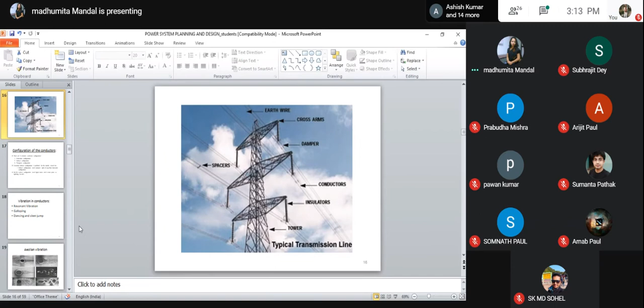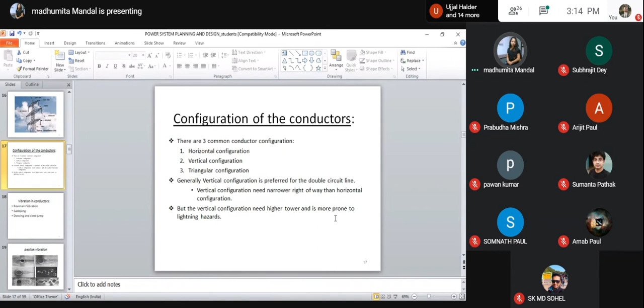Configuration of conductors. There are three common configurations. We already discussed this. So configurations: horizontal, vertical, and triangular. Generally, vertical configuration is preferred for the double circuit line. Vertical configuration needs a narrower right of way than horizontal configuration. But in case of vertical configuration, the problem is that it needs higher towers and is more prone to lightning hazard.